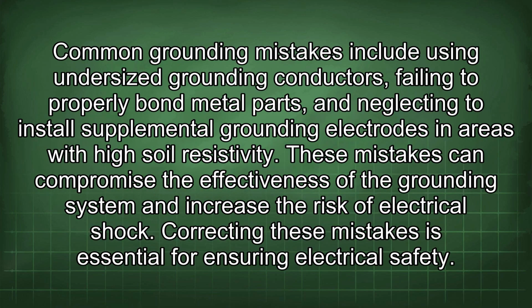Common grounding mistakes include using undersized grounding conductors, failing to properly bond metal parts, and neglecting to install supplemental grounding electrodes in areas with high soil resistivity. These mistakes can compromise the effectiveness of the grounding system and increase the risk of electrical shock. Correcting these mistakes is essential for ensuring electrical safety.